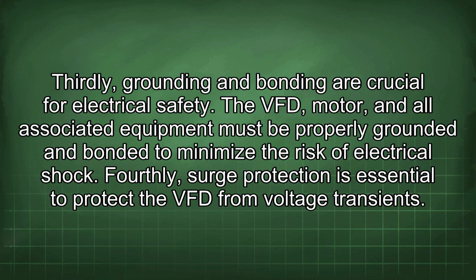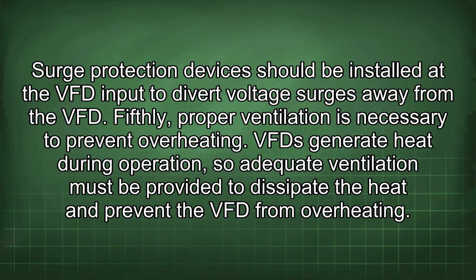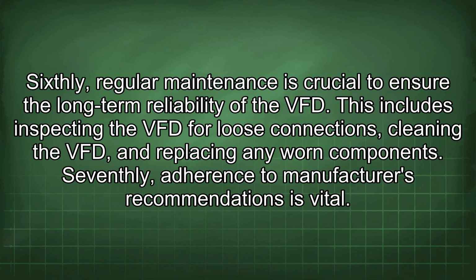Thirdly, grounding and bonding are crucial for electrical safety. The VFD, motor, and all associated equipment must be properly grounded and bonded to minimize the risk of electrical shock. Fourthly, surge protection is essential to protect the VFD from voltage transients. Surge protection devices should be installed at the VFD input to divert voltage surges away from the VFD. Fifthly, proper ventilation is necessary to prevent overheating. VFDs generate heat during operation, so adequate ventilation must be provided to dissipate the heat and prevent the VFD from overheating.